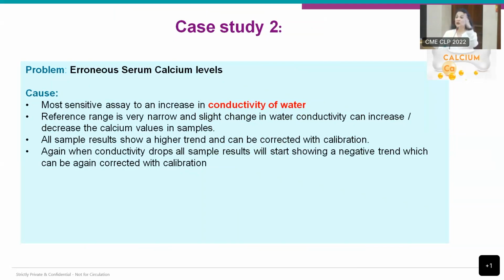ये मतलब graph set होता है calibration का, right? When you do it. Now when you recalibrate with a poor conductivity, high conductivity, graph will reset at a different point. ऊपर का नीचे आ जाएगा. Now when the conductivity improves, why will it improve? Water quality ठीक भी होगा, right? Then what will happen? Are the values coming correct in that case? Water improves, graph is set low, which is incorrect, and you will end up in a very big problem. This happened to us. We have done this before. I don't want all of you to do this. I don't want you all and your lab to do this because never calibrate in the first instance unless you know why we are calibrating. If it reverts back to normalcy, you will never be able to justify why you have given wrong reports.